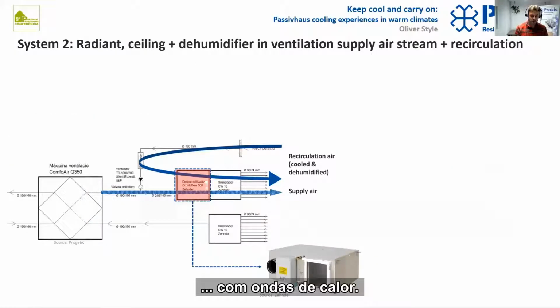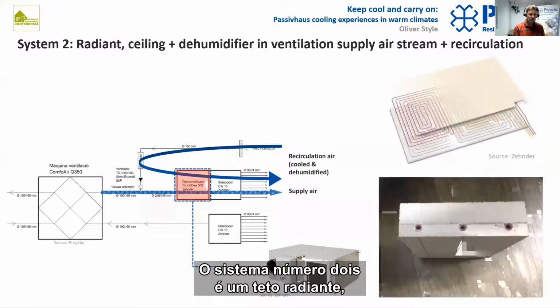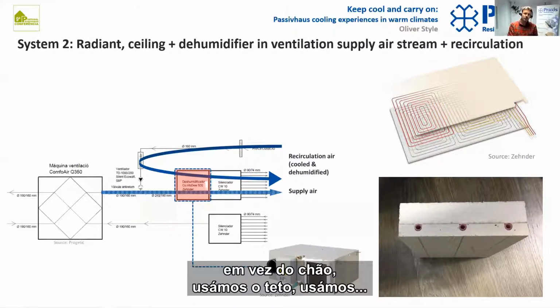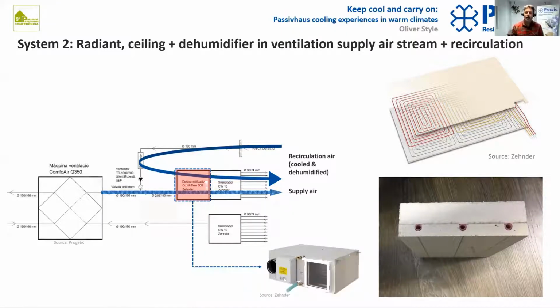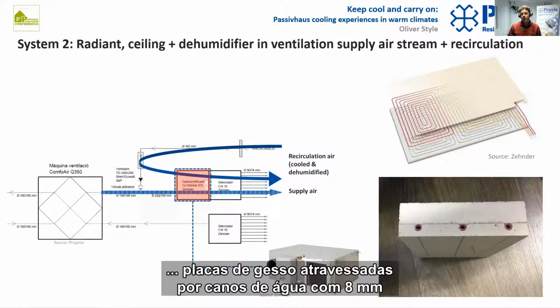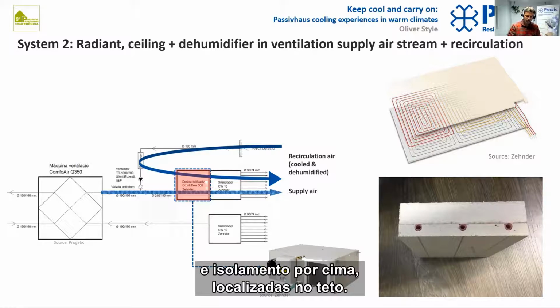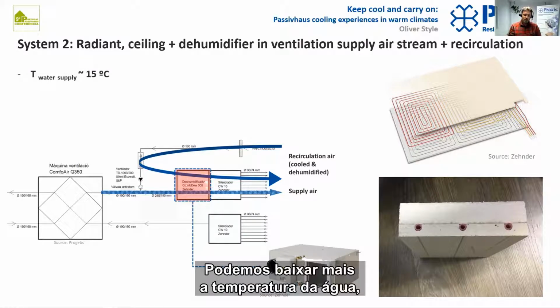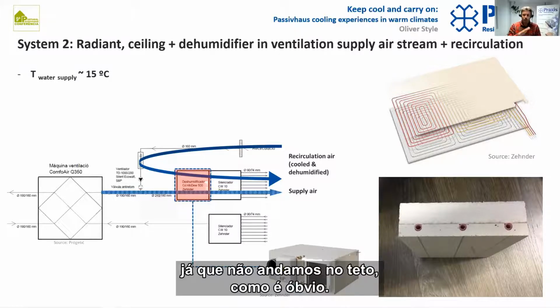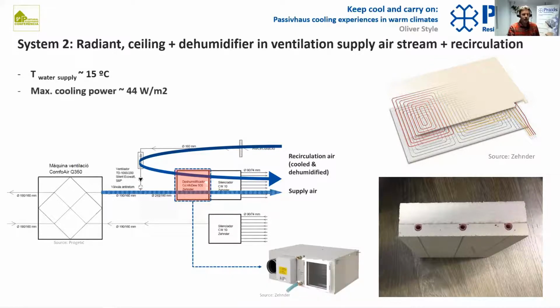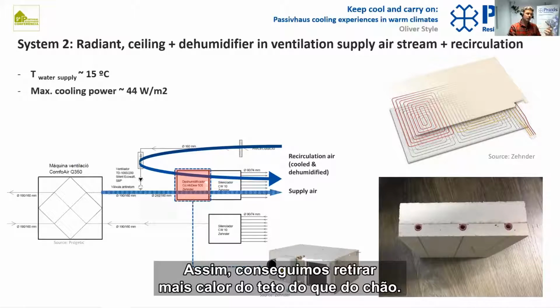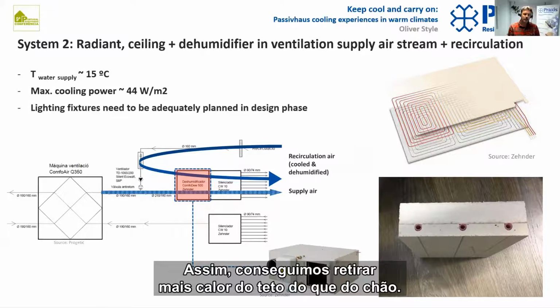So this system number 2 is a radiant ceiling. So instead of using the floor, we're using the ceiling. We're using plasterboard with 8mm water pipes running through them and insulation on top. These are located in the ceiling. We can run water temperature slightly lower than on the floor because of the comfort reasons. We don't walk on the ceiling, obviously. So we can get a little bit more heat out of a ceiling than we can out of a floor.